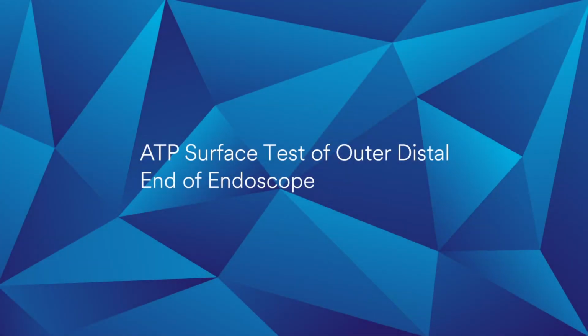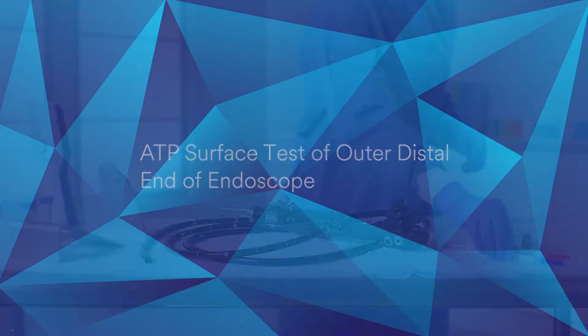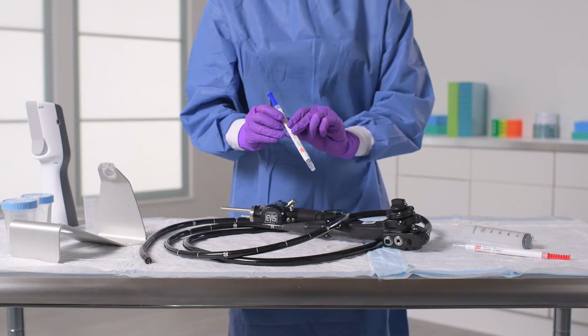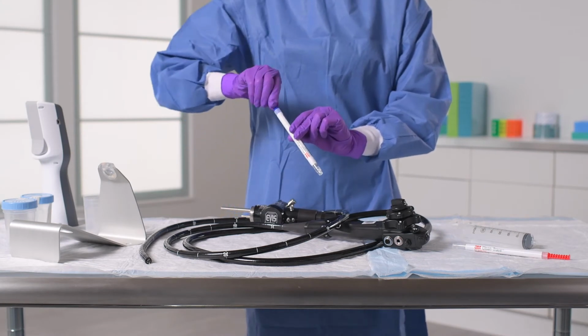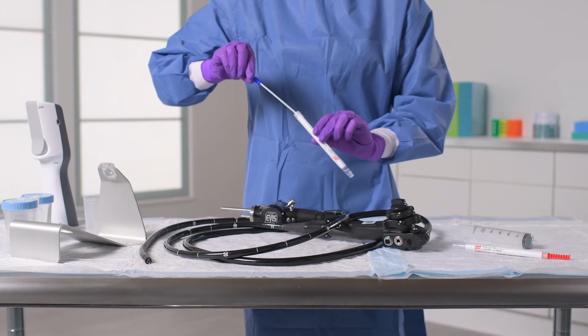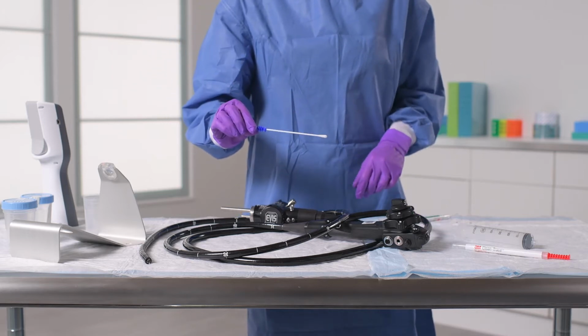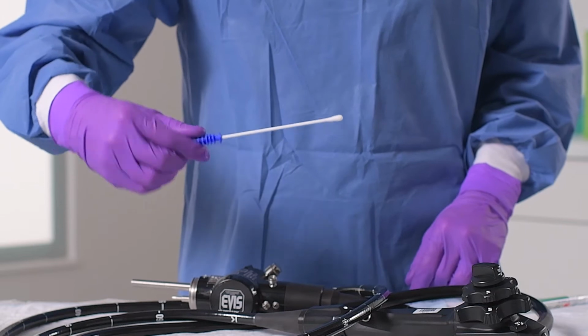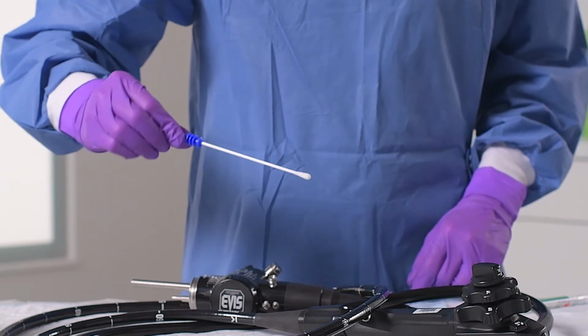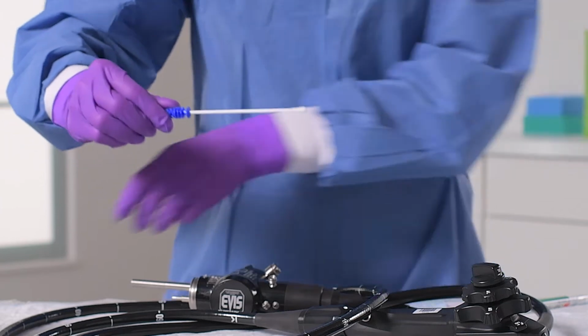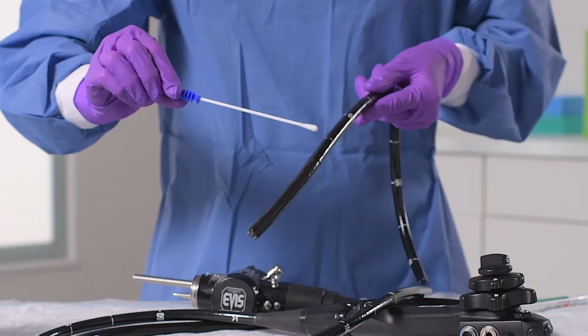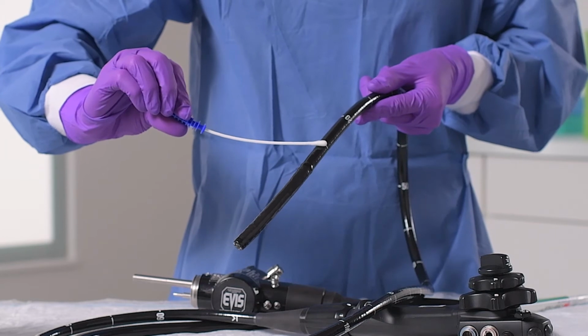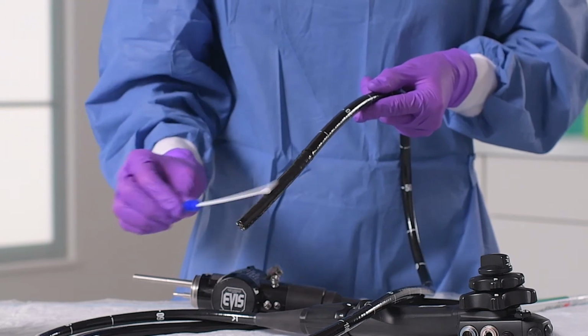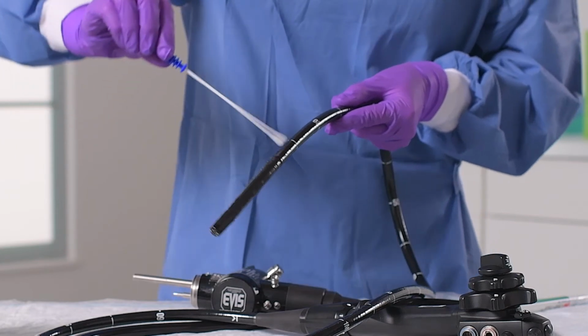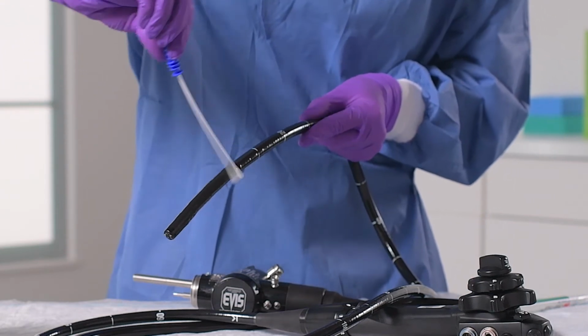When you are ready to collect your sample, start with the surface test of the outer distal end of the endoscope. Remove the surface test swab from the device sleeve, taking care to touch only the blue handle. Do not let the swab touch any surface except that which is to be sampled. Hold the test between thumb and forefinger so you can easily rotate the swab. Touch the swab to the outer distal end and apply enough downward pressure to cause the wand to flex. Move your swab back and forth to test all sides of the distal end for a length of about 10 centimeters or up to the first hash mark.